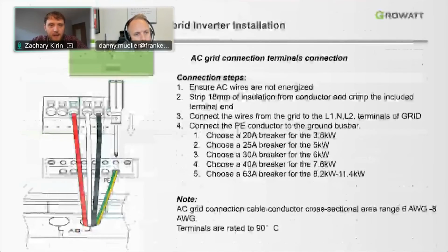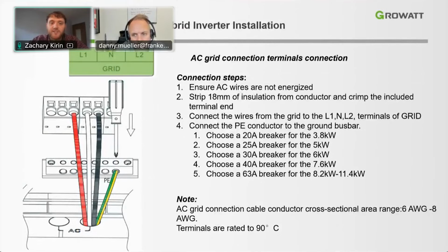Good. And then onto the AC side. So the AC grid connection terminal ensures that the AC wires are not energized first. So it's important that we make sure the grid disconnect is not on and those wires are not energized. Again, we'll strip 18 millimeters of insulation from the conductor and then crimp on those included terminal ends. It's a recommendation. Connect the wires from the grid to the L1 and L2 terminals of the grid port, as shown here. And the breaker sizing depends on what type of power range inverter you have. So for the 3.8, the manual recommends a 20 amp breaker, and then all the way up to a 63 amp breaker for the 8.2 and the 11.4 kilowatt inverters.